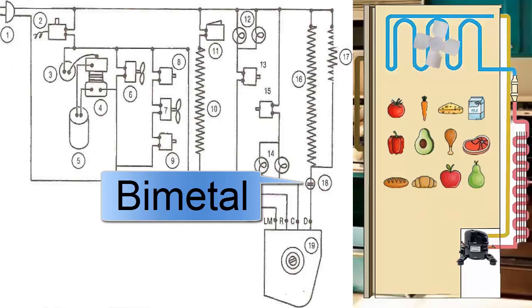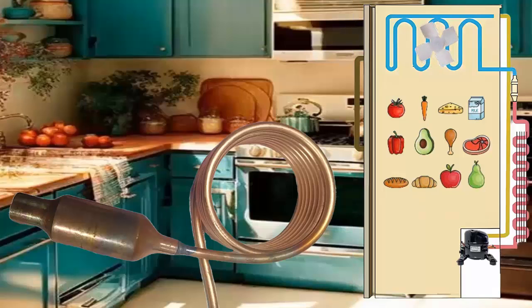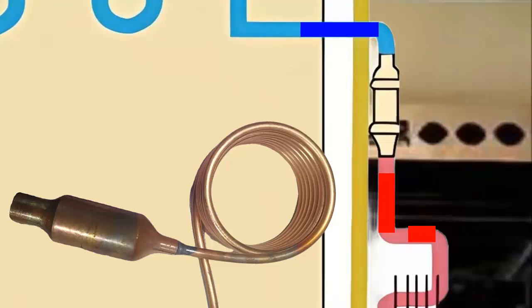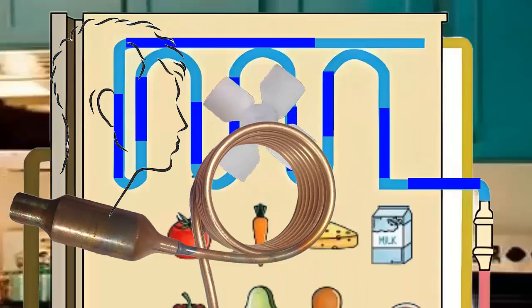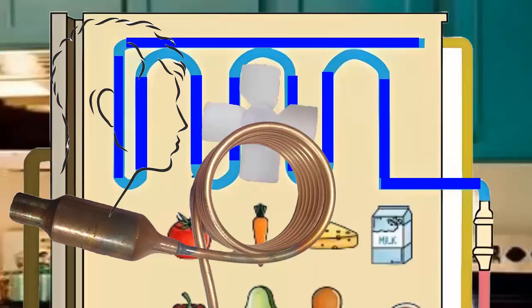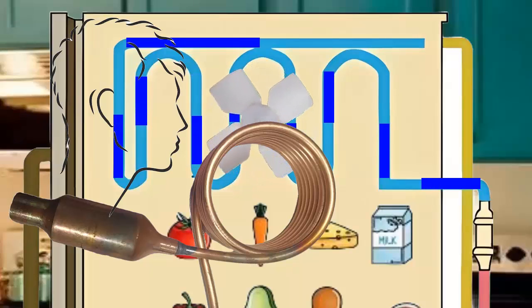Method 6: Observation of the Capillary Tube. Observe if there is freezing in the capillary tube or only parts of the freezer evaporator. In this case, the problem is an internal obstruction in the capillary tube or some internal tube of the evaporator.